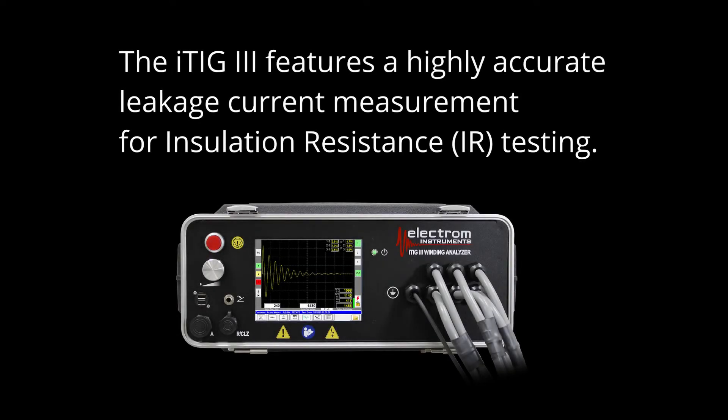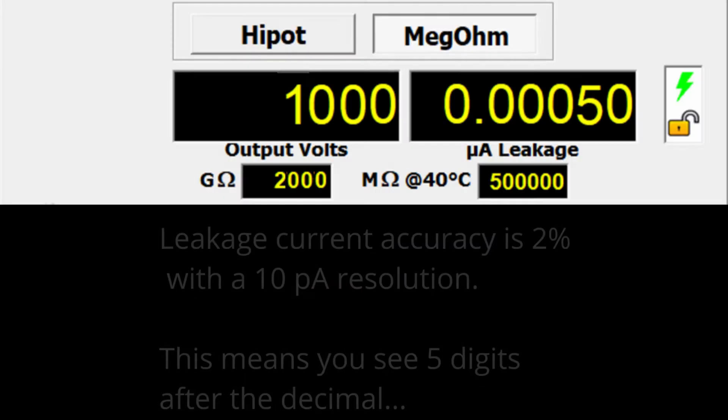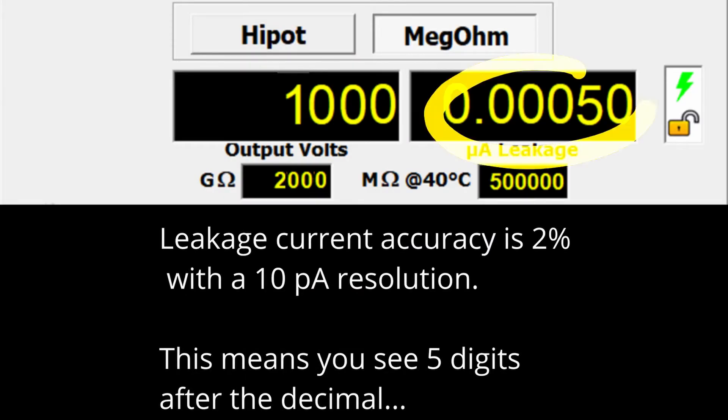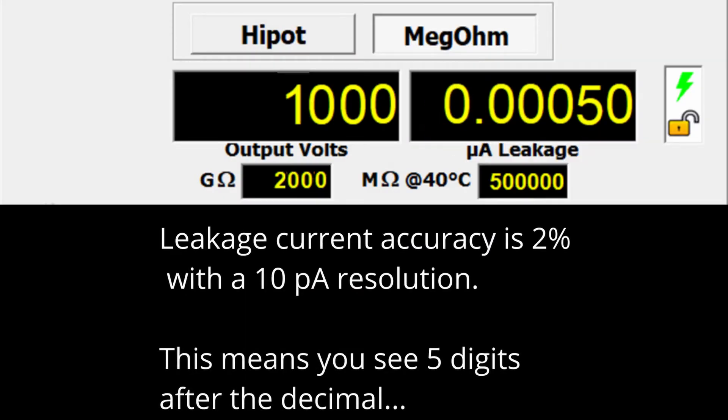The iTig3 features a highly accurate leakage current measurement for insulation resistance testing. Leakage current accuracy is 2% with a 10 picoamp resolution. This means if the tester displays in microamps, you see five digits after the decimal.